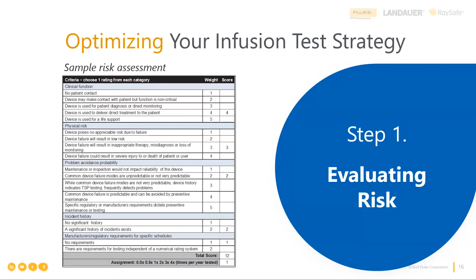So automating the tests, in terms of automatic documentation, is a really helpful thing. If we have interoperability between this automation of the workflow and our infusion electronic analyzers, where we can collect the information automatically for each measurement, that really helps speed things. It helps us reduce human error. It helps us be more compliant to the source of the pass-fail criteria, the testing limits, which in our case is going to be the manufacturer's specifications in their test procedure from the service manual of the device.